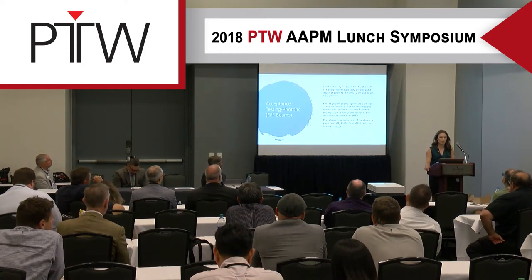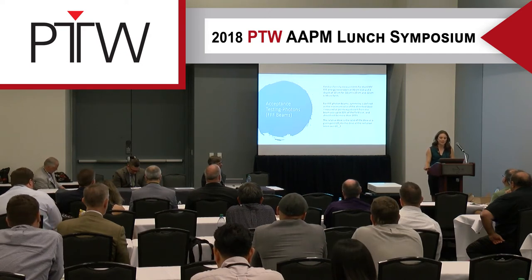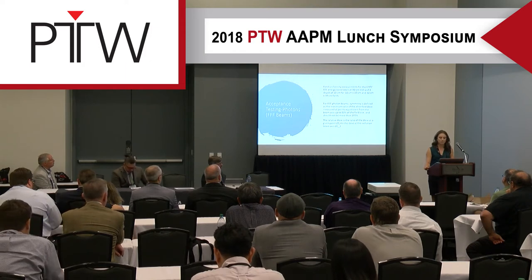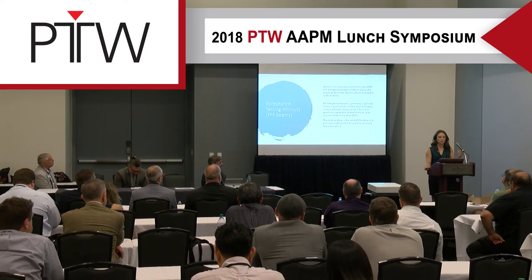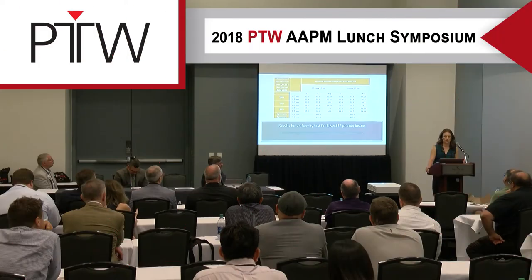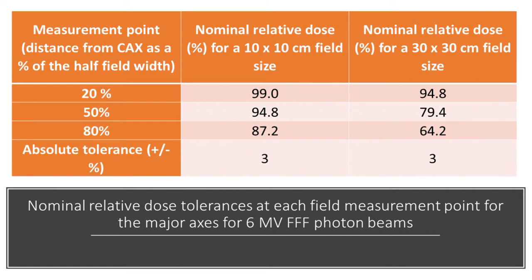We also accepted and commissioned the 6MV flattening filter-free energy. Our existing Versa is capable of 10MV FFF, but for our two new ones we just commissioned the 6MV. Measurements were taken at 90CM SSD at 10CM depth for 10x10 and 30x30 field sizes. Elekta defines FFF symmetry as the maximum ratio of absorbed dose at equidistant points from the central axis up to 80% of the field size, all within 103%. For all of our results, we were well within that tolerance.